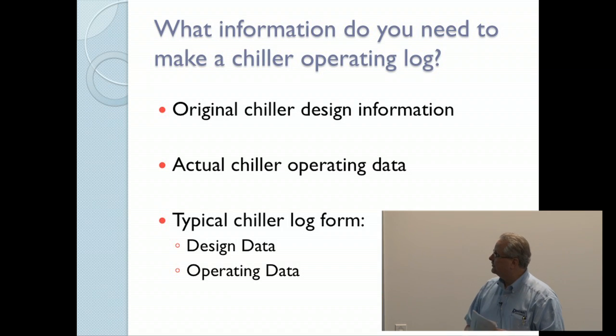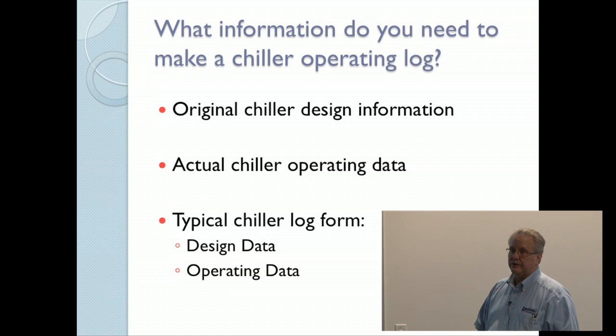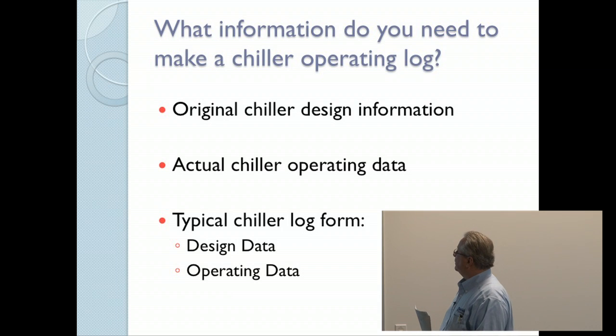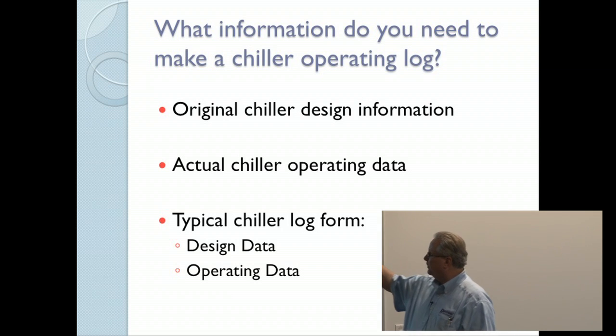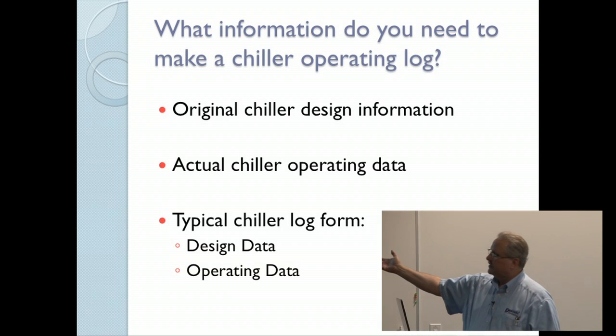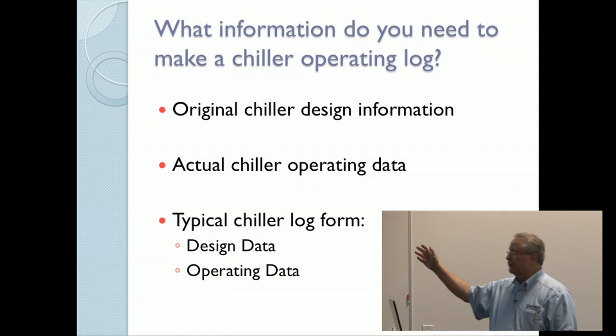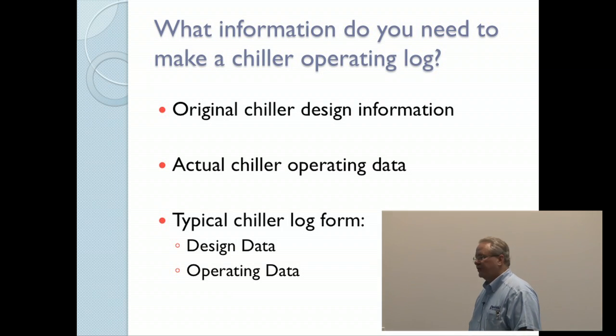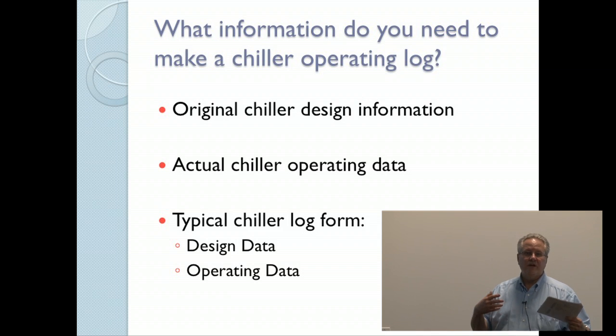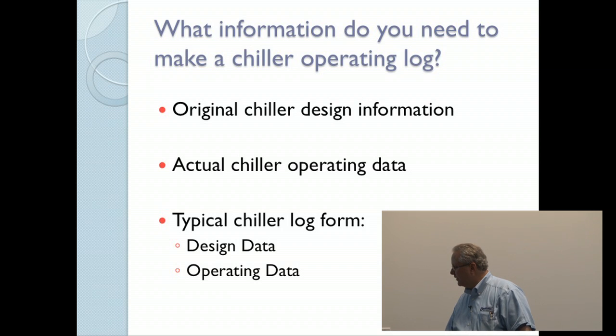Down in southeast Kansas, this is a 300-ton York centrifugal that was 15 years plus old. I was able to get the performance data, the amount of refrigerant, the amp draws, and all the water and pressure drop conditions. These are available from the manufacturers. If it's a smaller unit, you can at least get the catalog data, or look on the drawings and see what the engineer originally designed the parameters to be for that application.